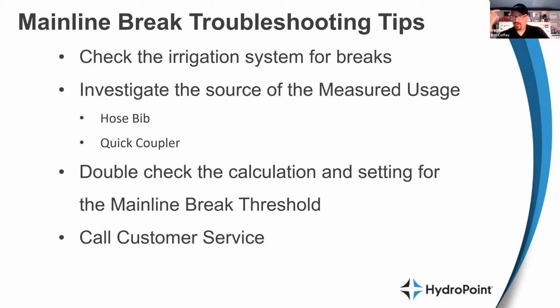If you turn on the master valve override, that will help you. The information on the display will help you, right? You can see what your flow sensor is measuring right on the panel, on the face of the controller, and it'll tell you how many gallons per minute your flow sensor is measuring. So make sure that you're starting at the beginning, turning on that master valve and watching the number first. And if it continues to spin, you go out, walk the main line and look for places that water might be disappearing. Keep an eye out for on-site management, right? If you've got hose bibs or quick couplers, it's easy to pass the limits with those things. If you plug in one too many quick couplers, you can pass that mainline break threshold in a heartbeat.